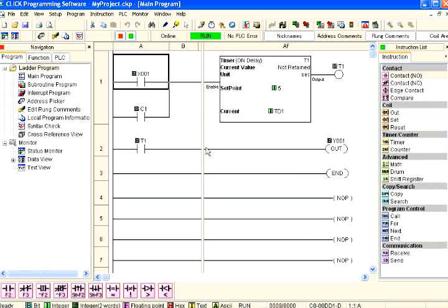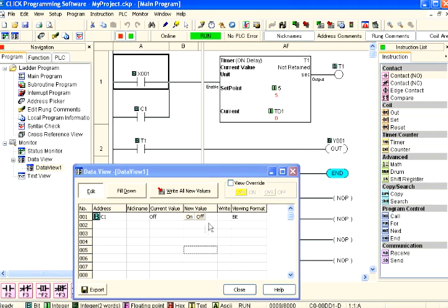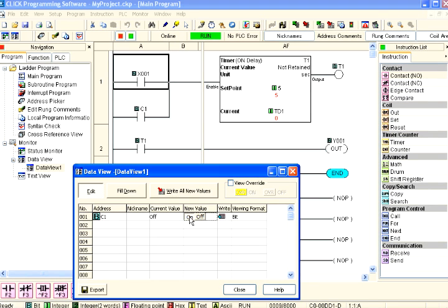The quickest way to do this is to click on the status monitor icon as shown here. We are finally ready to test. We need to override the current value of our internal C1 bit. We can do this by double clicking the On button in the New Value column of our C1 entry in Data View as shown here. The C1 bit will change from off to on.